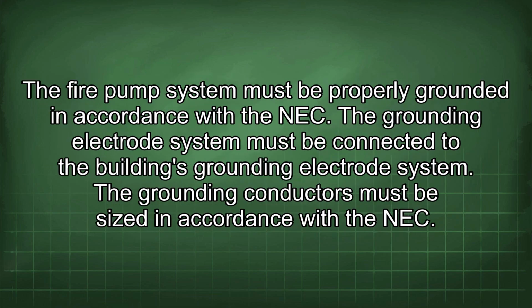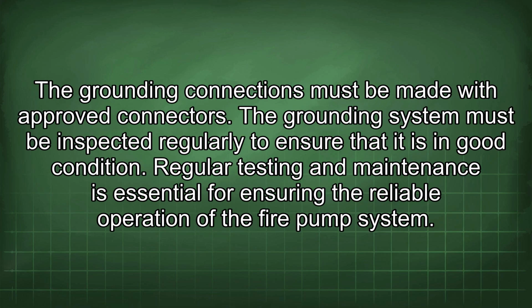The fire pump system must be properly grounded in accordance with the NEC. The grounding electrode system must be connected to the building's grounding electrode system. The grounding conductors must be sized in accordance with the NEC. The grounding connections must be made with approved connectors. The grounding system must be inspected regularly to ensure that it is in good condition.